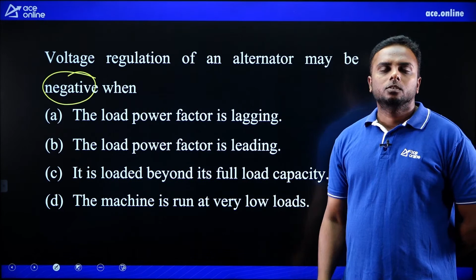Other options: it is loaded beyond its full load capacity, or the machine is run at very low loads. So regulation being positive, negative, or zero depends on power factor, and also on load, but mainly it depends on the power factor of the load. So here we have lag and lead as the two options; where do we get negative regulation?